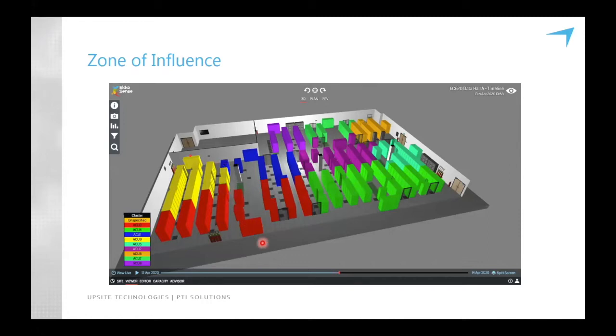How this is done is that the software is constantly monitoring the intake temperatures to the cabinets, as well as the supply temperatures from the cooling units. And as those fluctuate, the software is able to match up the zone of influence and identify the plumes of cooling air under the raised floor. This becomes very useful in identifying the capacity availability for deploying high density equipment, as well as solving some recirculation problems when they occur in rooms.